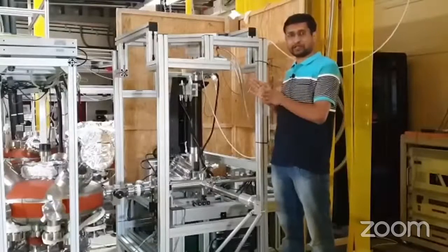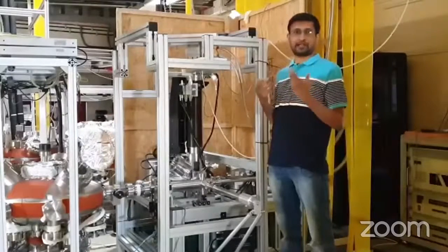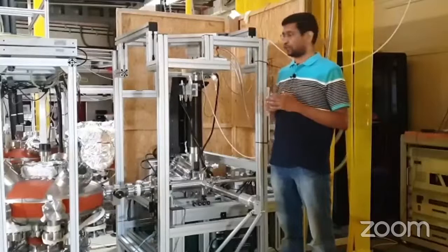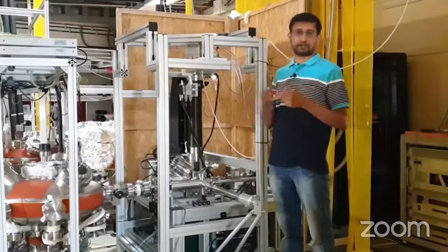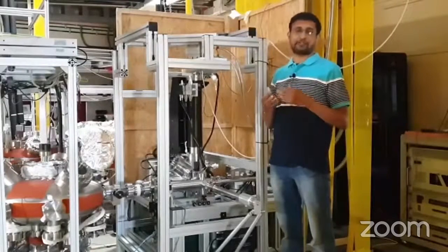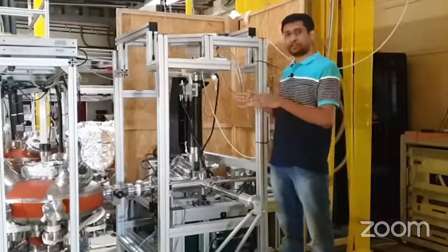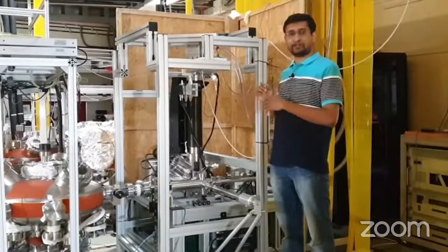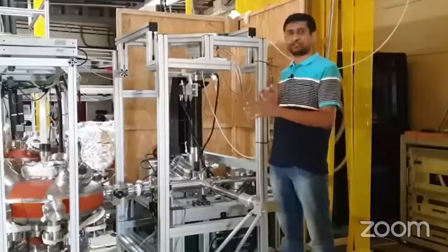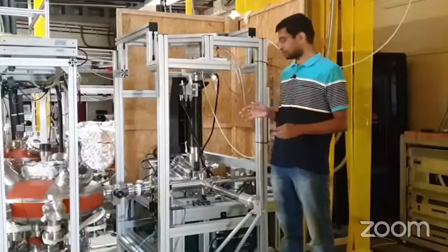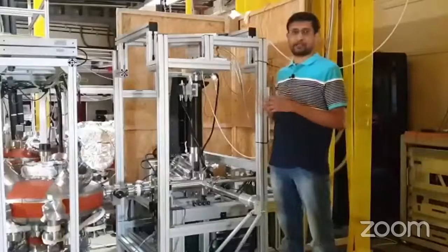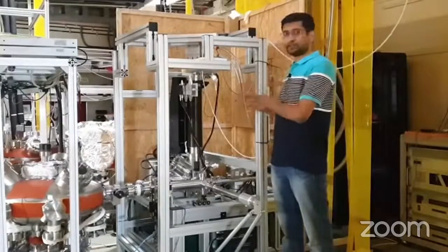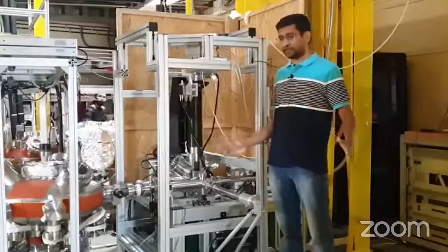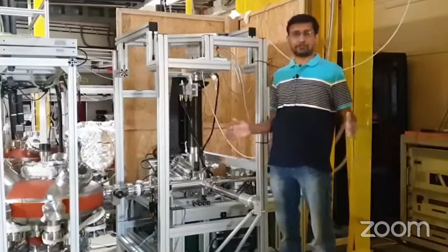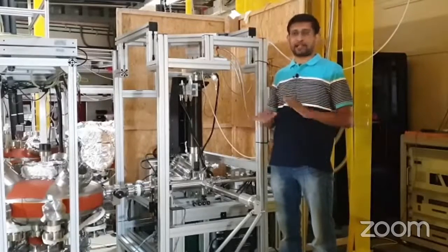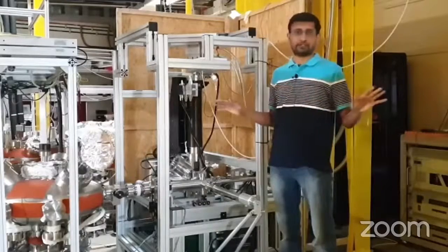So now the instrument here is prone to any source of external noise. And noise can be of various kinds. Mostly it's acoustic, electrical, and vibrational. We have made sure that we can decouple all these three sources of noise by a judicious choice of the design of the system. Now let's start with the vibrational noise. We have this instrument housed on a big chunk of concrete mass. It's almost 50 tons of concrete. It's sitting on sand and completely decoupled from the building foundations.